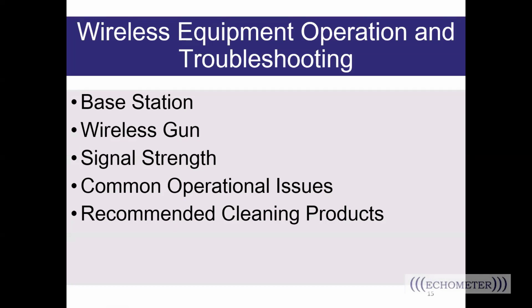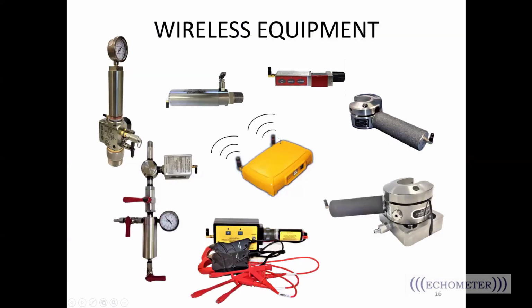So let's switch over to talk about wireless equipment. So we're going to talk about the base station, the wireless gun, troubleshooting signal strength issues, look at some common operational issues, and then some recommended cleaning products. So here's the wireless equipment. So you see the gas guns here. This is a wireless pressure transducer, and it's separate from the pressure transducer. It's inside the wireless gun itself.